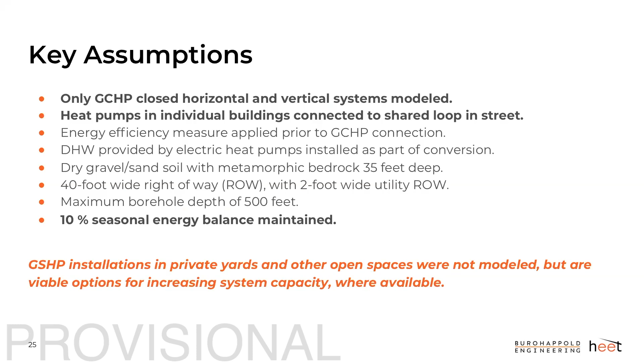A key point: we assumed the system would maintain a seasonal energy balance of about 10%, meaning the heat put into the ground and the heat pulled out during heating and cooling seasons is roughly the same. We did this to avoid thermal degradation—an imbalance between heat in and heat out could lead to adverse conditions, either freezing the ground or overheating it, which would diminish the system's capacity and potentially cause environmental issues. We wanted to avoid that.